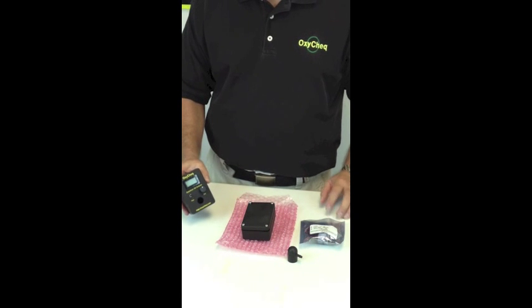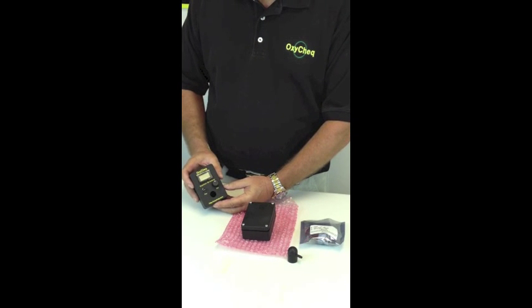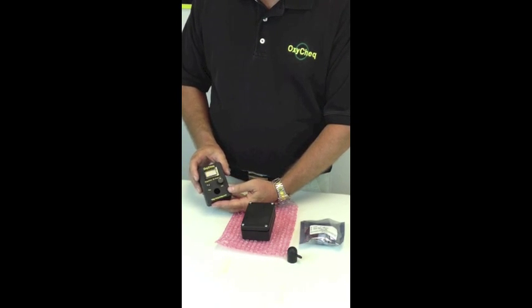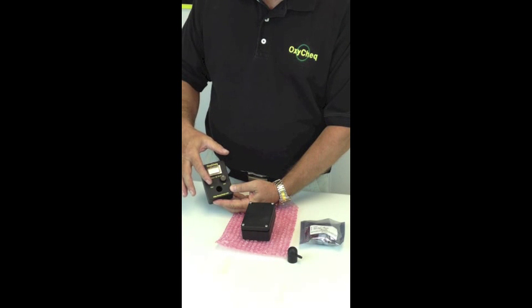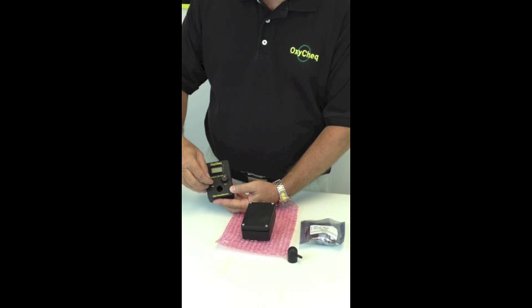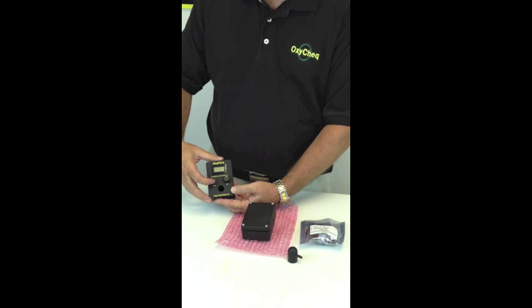Prior to installing the sensor in the analyzer, there's a couple of things that we should inspect first. Your on-off switch and your calibration knob. On the on-off switch there's a little rubber black boot. We'll lift that up, which will unlock the switch itself, and we will turn it up in the up position. Once we do that, we'll see the display is turned on and there will be numbers on the display itself. The center position is off. The down position is display on with backlight.